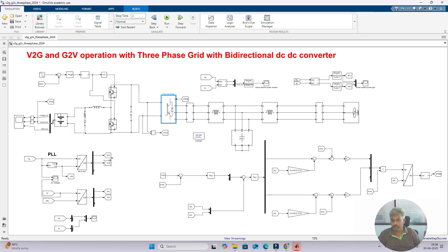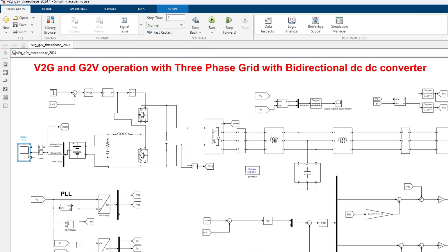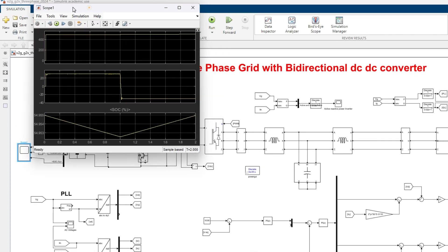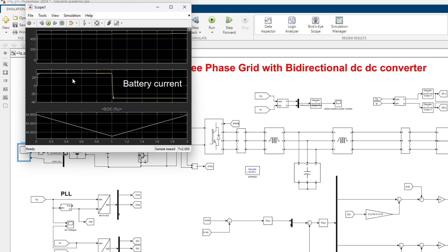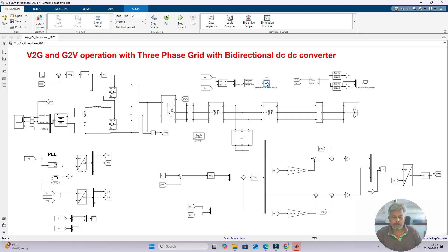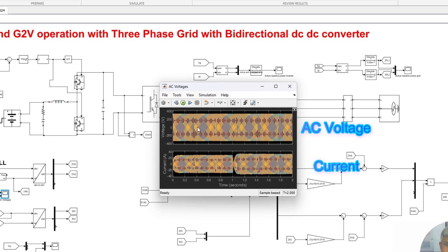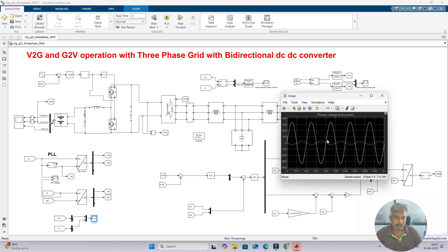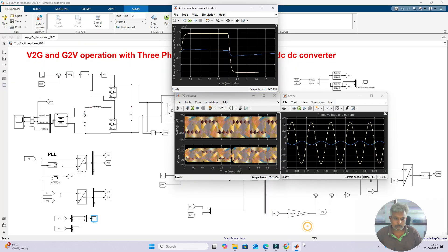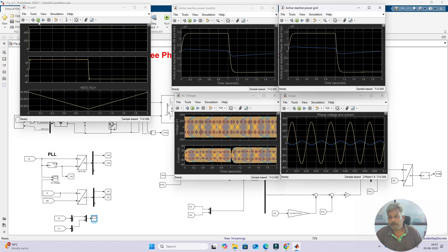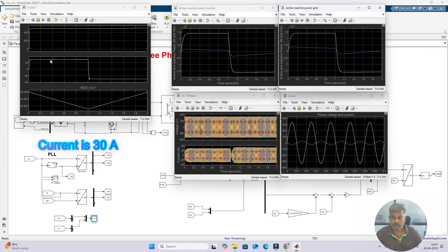Now I am going to explain the results. The scopes show battery voltage, battery current, and battery SOC, as well as inverter active and reactive power, grid point active and reactive power, AC voltage and current at the point of common coupling, and phase voltage and current. Initially, from 0 to 1 second, the reference current is fixed at +30 A, which means positive current, so the system acts as vehicle-to-grid mode.